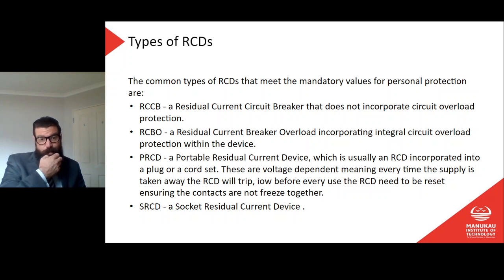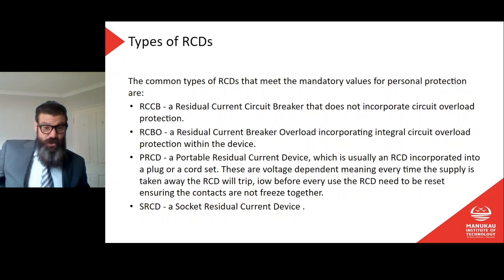Interesting one, something that I've come across. I've talked about this before in class, but something I've come across in my own home recently that I've never seen before is the bathroom downstairs has the SRCD, the RCD at the socket, and then the bathroom upstairs is also controlled from that same socket somehow. So they've wired the sockets in the upstairs bathroom to the RCD in the downstairs bathroom, which is weird, and it seems shady to me. It works, but there you go. So you might just come across that one day.